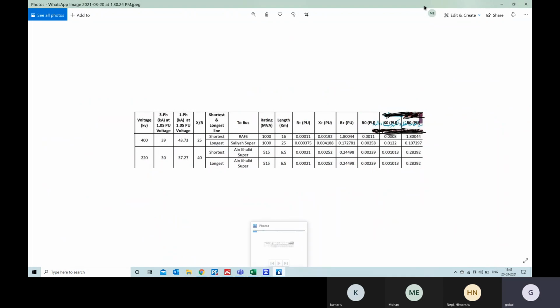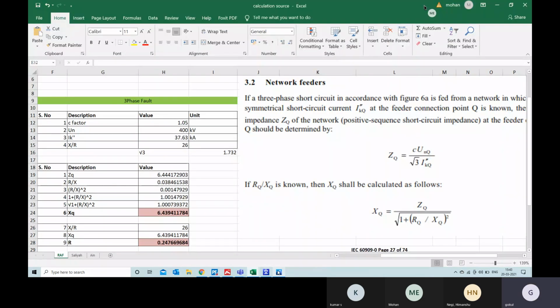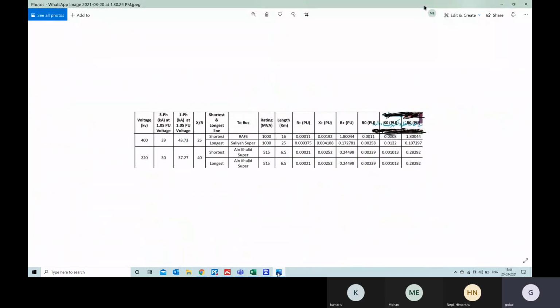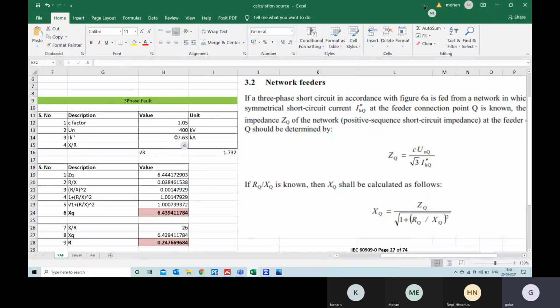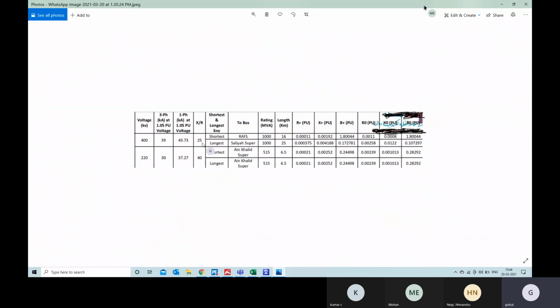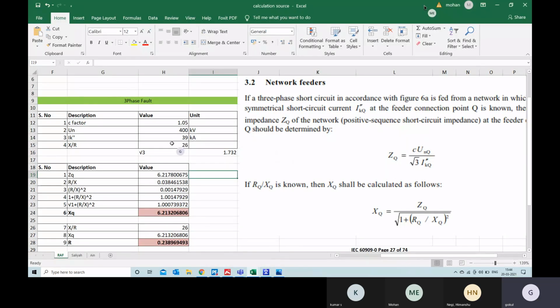I can change that to 39 itself, right? Just give me a minute. RAF, yes, 39. In our case it is 39, so 39 kiloamps. The X/R ratio is 26. Where I got the X/R ratio here is 25, so we can change this to 25 itself. We can go to the calculation and change that to 25.